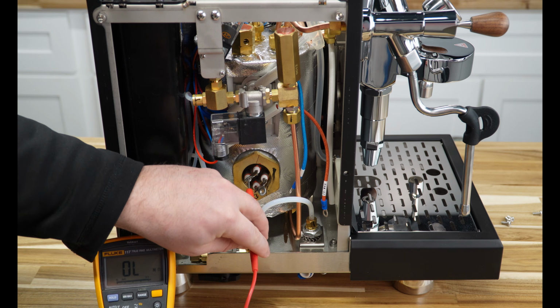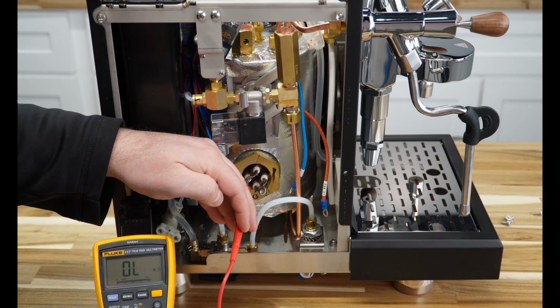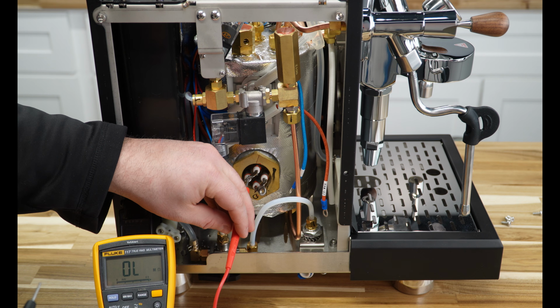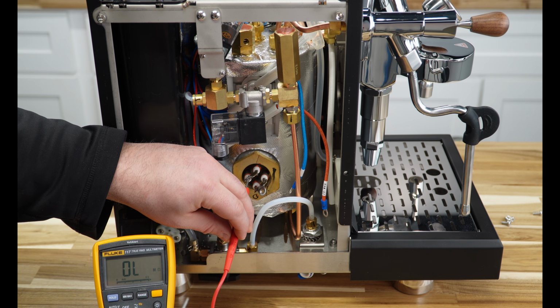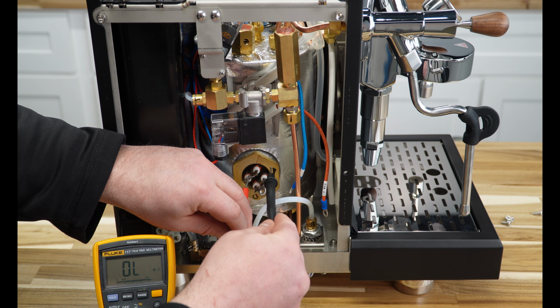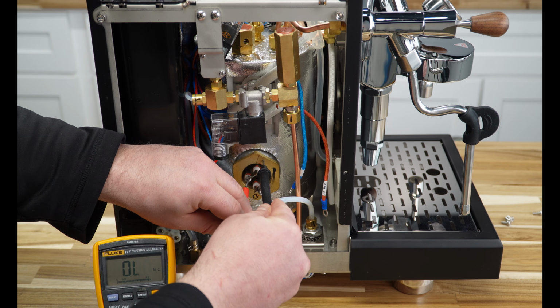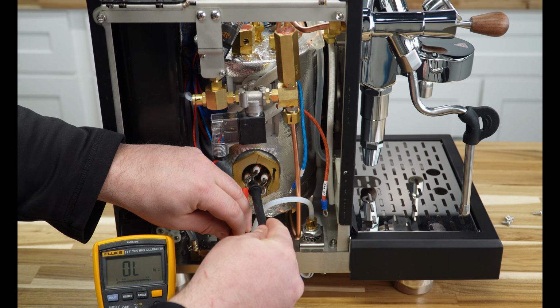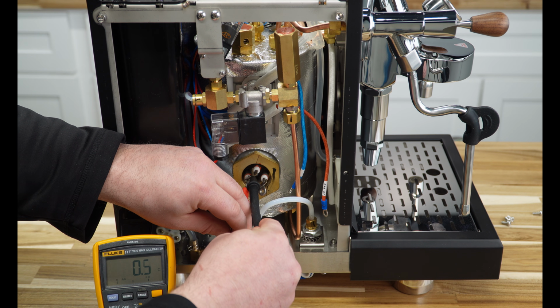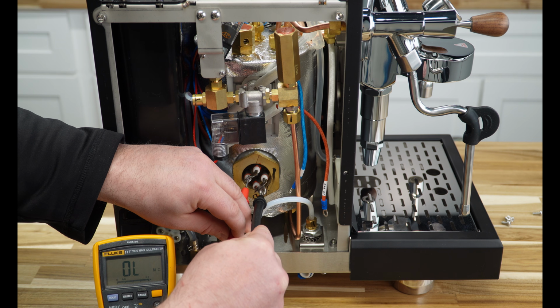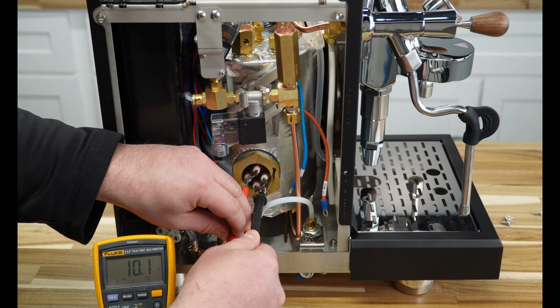Then I'd switch to check the other side of the heating element, since sometimes those pinholes only conduct electricity on one of the two sides. Again, this heating element is good. If we touch the probes together you'd see very low resistance, and touching side to side gives us that same 10 ohms we saw earlier.